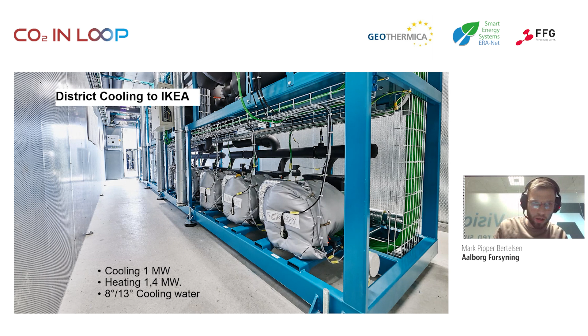This district cooling central can also be utilized just as a heat generation unit, working as a normal air to water heat pump with energy absorbers. If there's no cooling demand, we can take energy from the ambient air and provide district heating to the network as well.